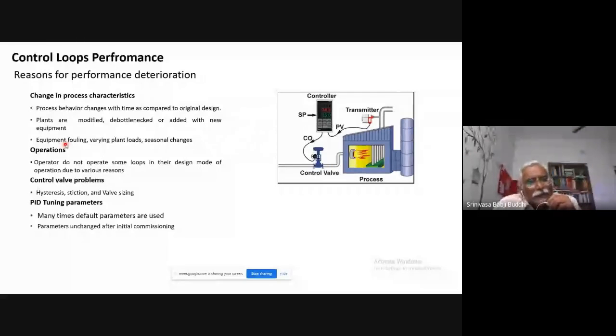Since operators do not have much time available to do a detailed investigation, what they do is they just put the loop in manual and operate it manually. That also will lead to deterioration in the PID control loop performance, because it has to be managed by the operators manually. And the next one is control valves. Many times we have hysteresis problems, stiction problems, valve sizing problems. All these problems again will lead to poor performance of the PID controller.